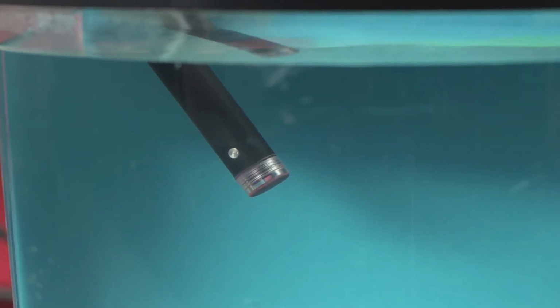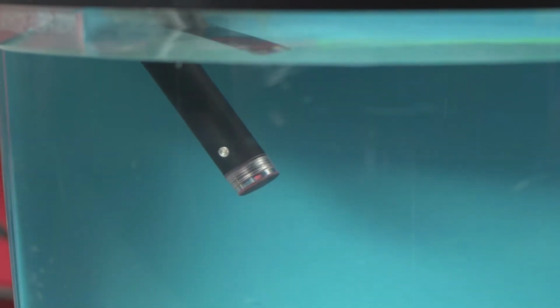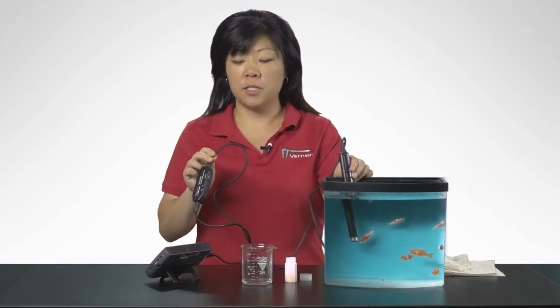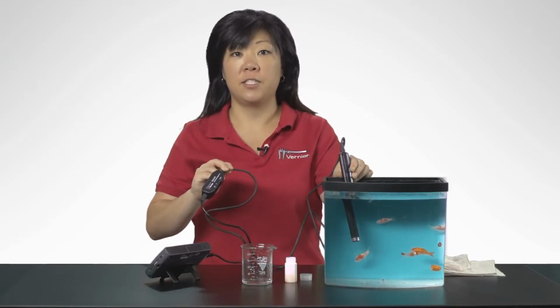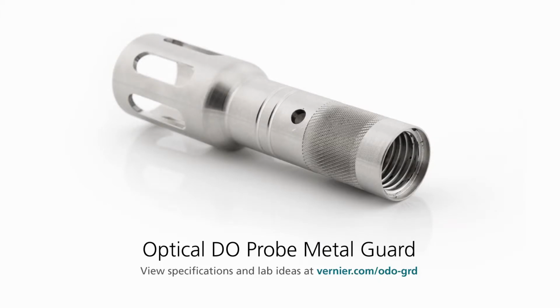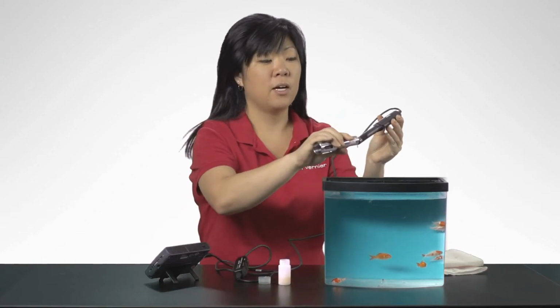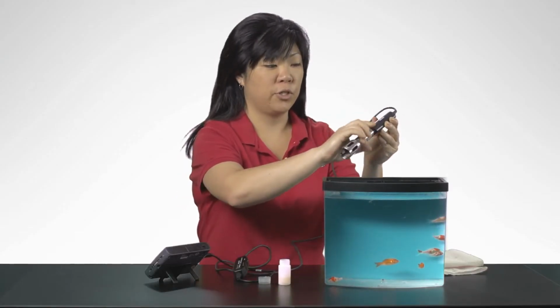The optical DO probe is designed so that it can be submerged in a water environment for extended periods of time. The body of the probe and cable are waterproof, but the box containing the microSD card is not. If you're taking measurements in the field, you may want to purchase the optical DO metal guard accessory to protect the cap and help weigh down the probe when submerged.